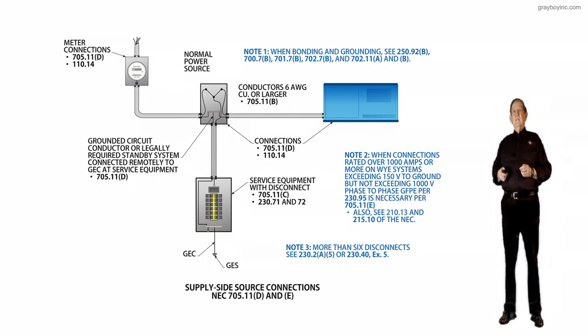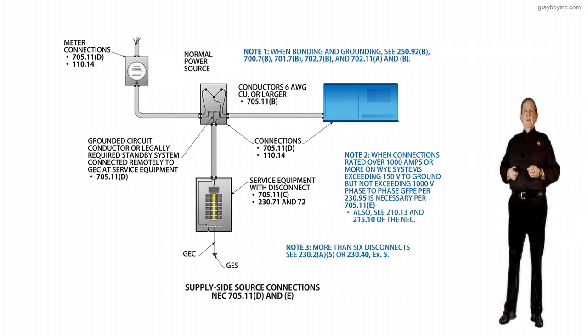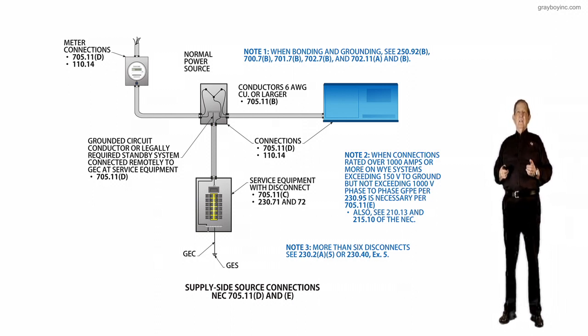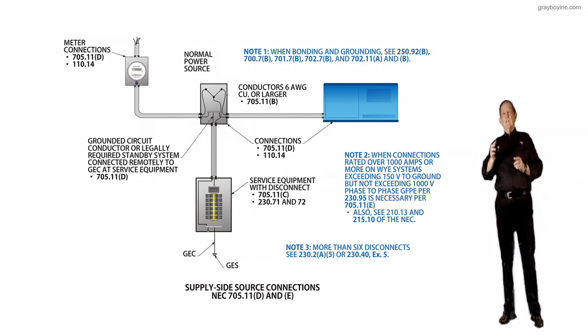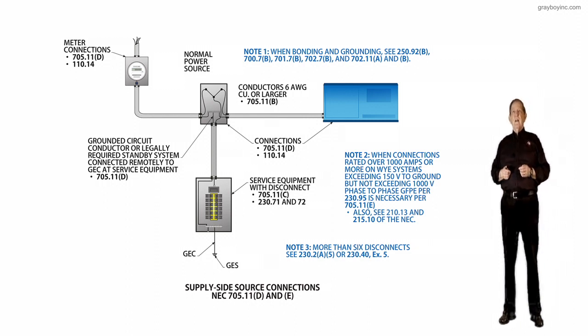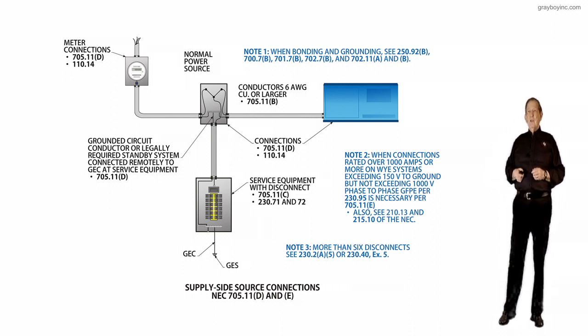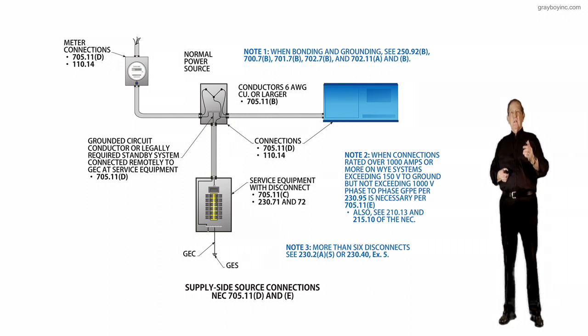Now, again, we reference the connections in the transfer switch and the generator. And we look at 705.11(D) as in dog, but 110.14 would regulate the size of the overcurrent device. If you're 100 amps or less, you're 60 degrees C terminals, with that, your equipment is marked 60/75. If you're over 100 amps, then you're automatically 75 degree C terminals. But we basically stated that you could take the 90 degree rating of the wire and derate it back to a usable 60 or 75, depending on the marking of the terminals, as outlined in 110.14.